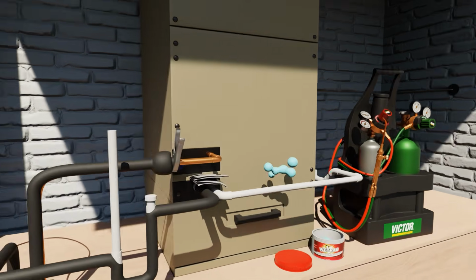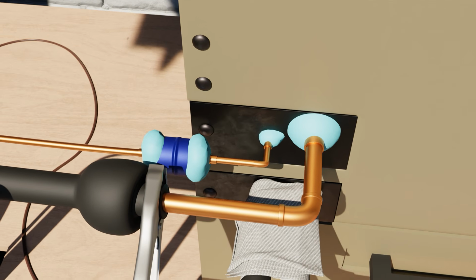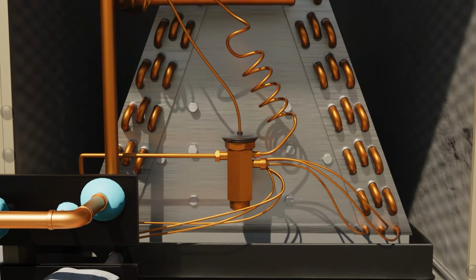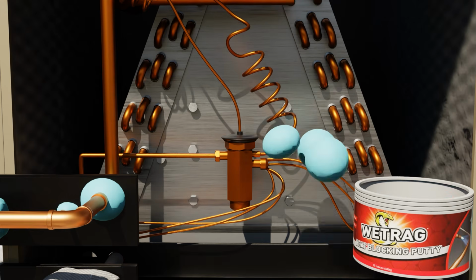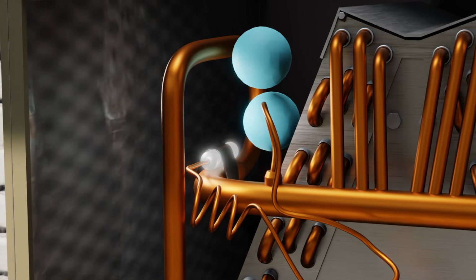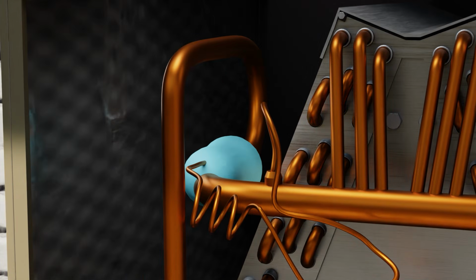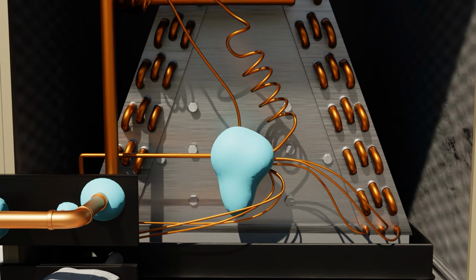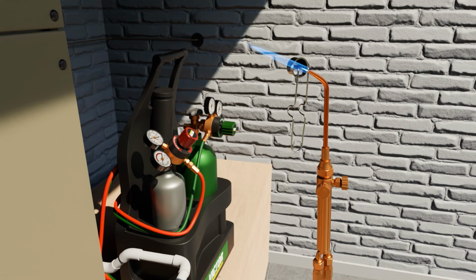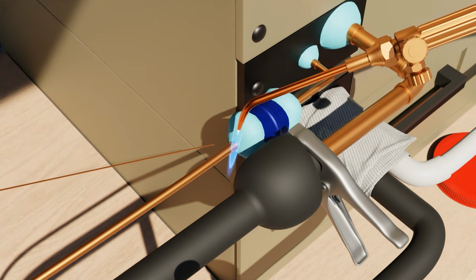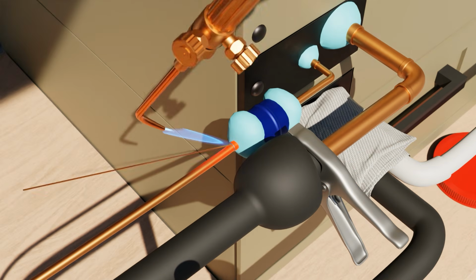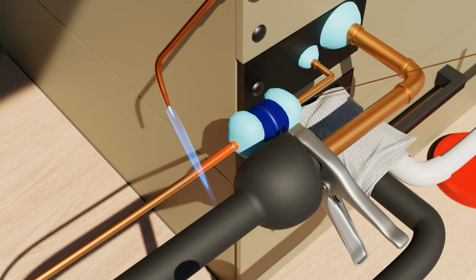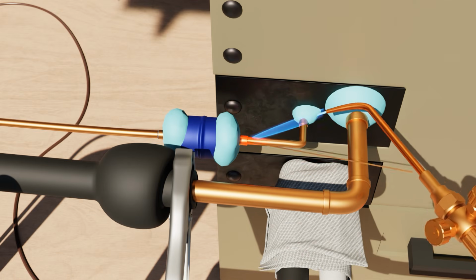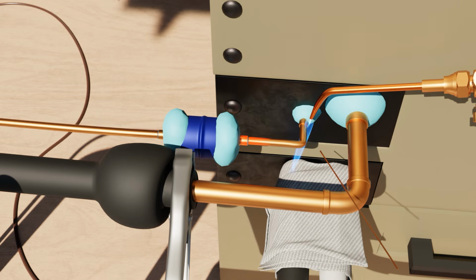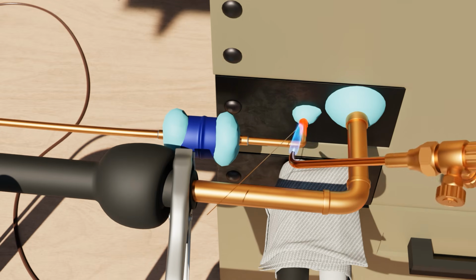When working indoors, make sure you're protecting all the surfaces and areas and that you still have your fire extinguisher handy. If you have a TXV indoors, protect the TXV and the TXV bulb. You could also just remove the bulb from the suction line to protect it if that's easier. Always be careful when handling a TXV or a TXV bulb. Now you do the same thing as before. You're going through the system, getting each joint to that dark cherry red to cherry red color, making sure you're drawing the alloy into the connection. Generally speaking, if you braze a connection, you can let it sit about 20 seconds, and then you can go ahead and cool it off with a damp towel or rag. Here we're showing brazing all of them before cooling them, but that's not generally how you do that.